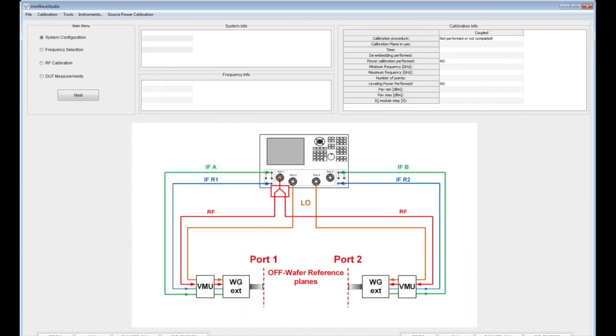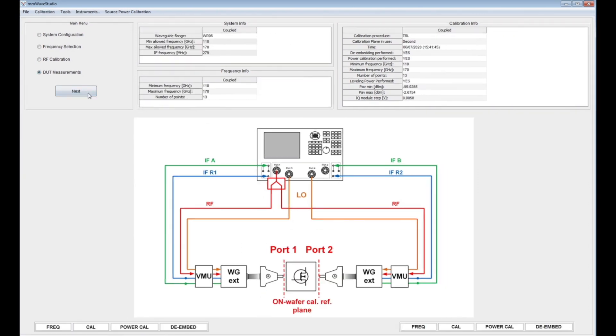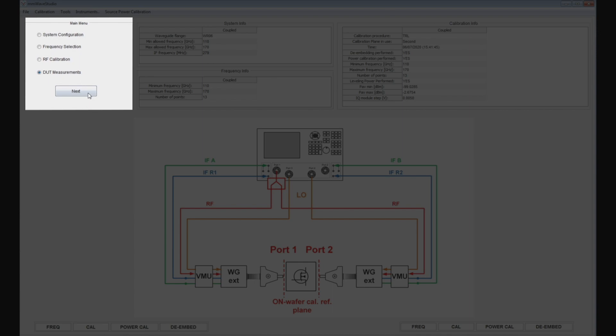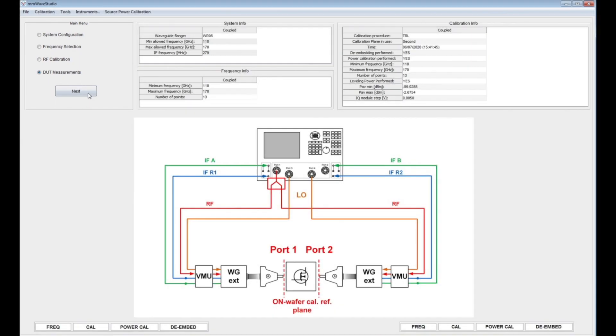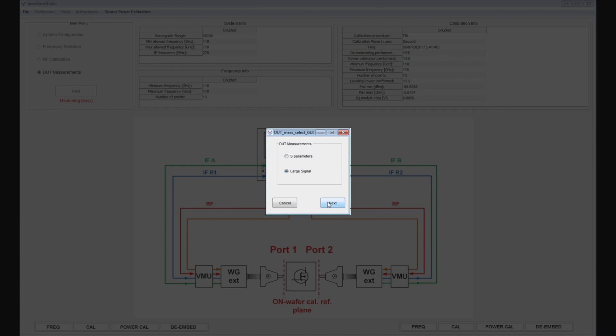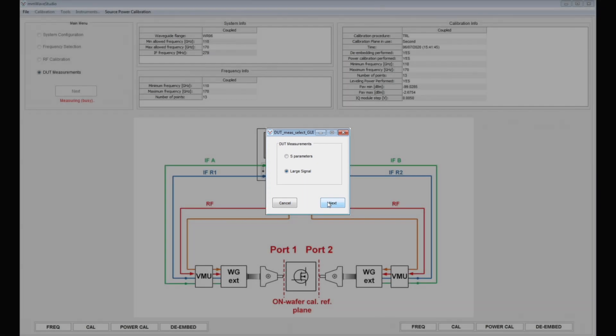Before we measure our device, we need to configure the setup. To do that, we need to start the Millimeter Wave Studio software suite. To perform a load pull measurement, we select the DUT measurement option in the main menu and click Next. A DUT measurement selection window shows up where we need to select whether we are performing a power controlled S-parameter or a large signal measurement. As we want to perform load pull measurements, we will be selecting the large signal option.